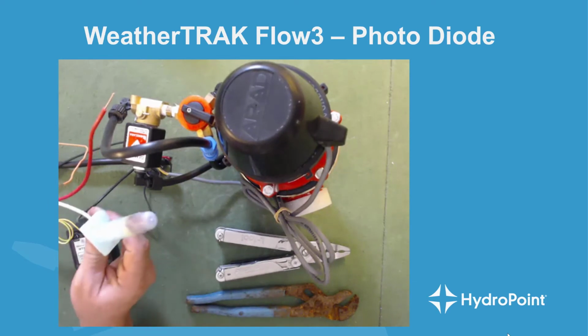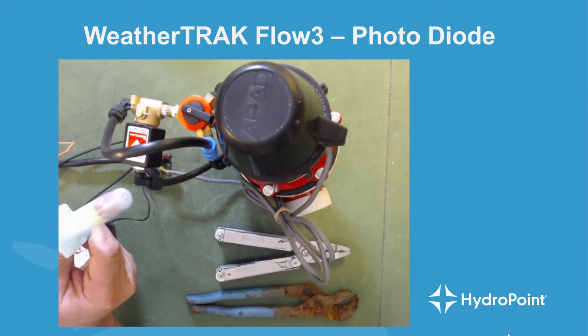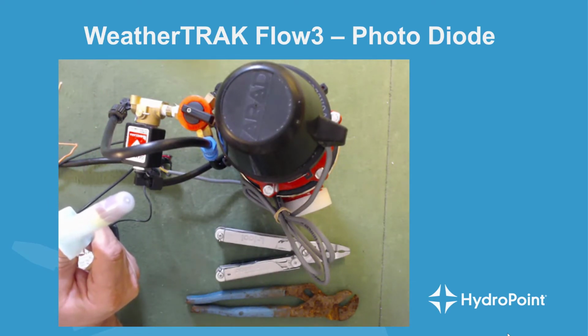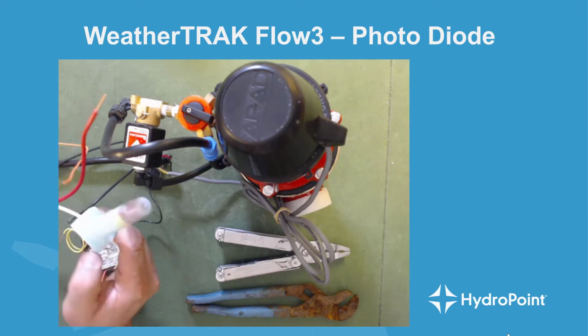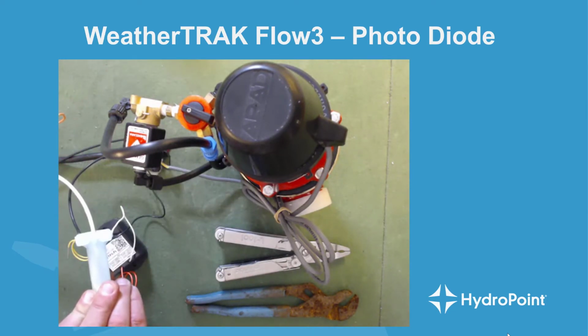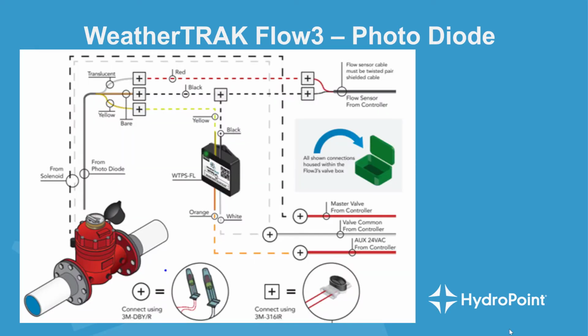And the key to a good DBY/R connection is to make sure that that wire nut is pushed all the way down into the top of the gel cap, so the gel covers the bottom of the wire nut and traps out any water or other contamination into the wire nut, and then make sure that the gel cap is completely closed tight around the wires. And once we've got the black and white connections knocked out, the rest are very straightforward. It's simply following the wire diagram to hook the wires coming in to the correct wires in the valve box.